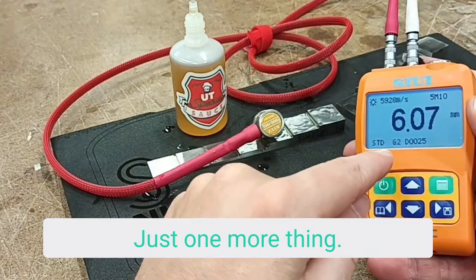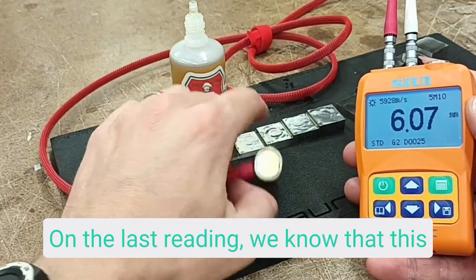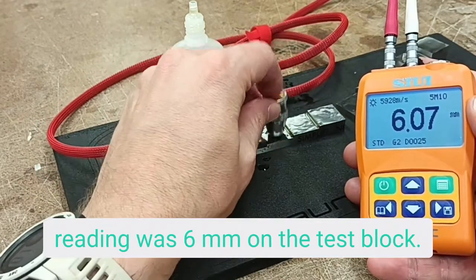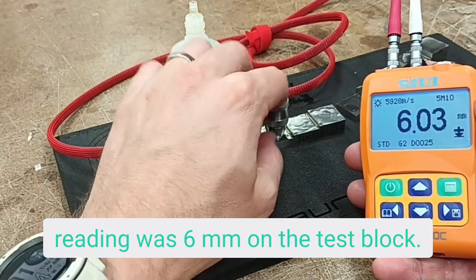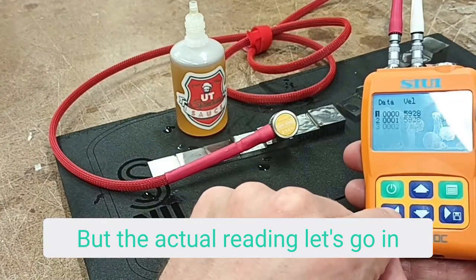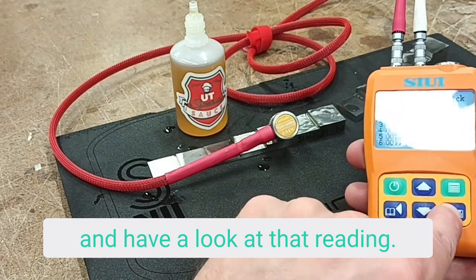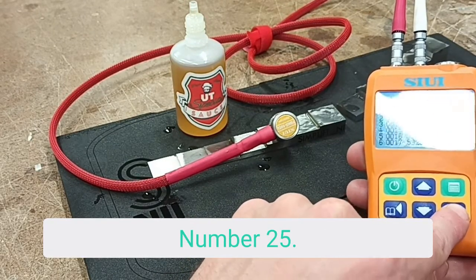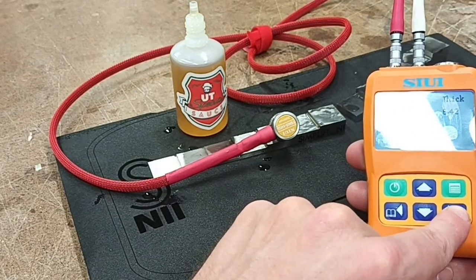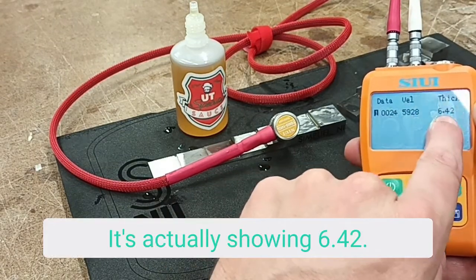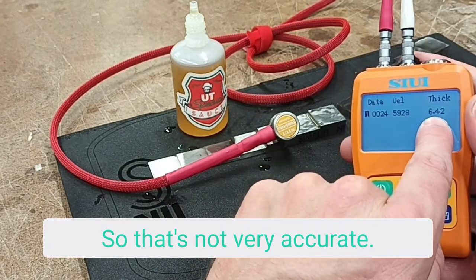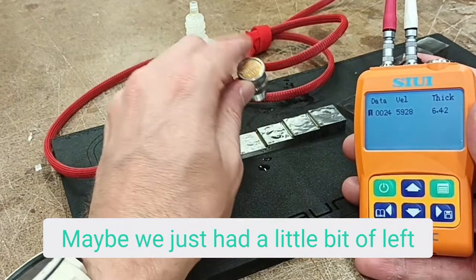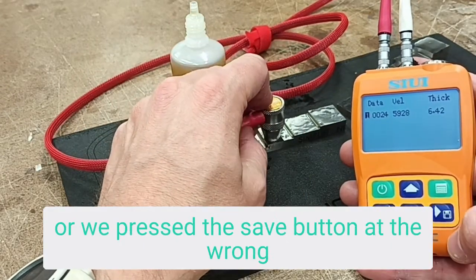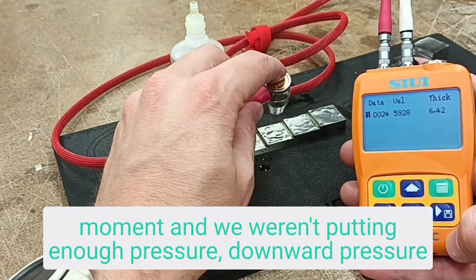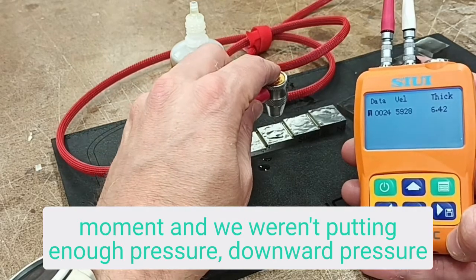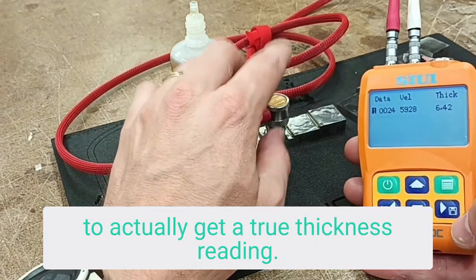Well, just one more thing. On the last reading, we know that this reading was 6 millimeters on the test block, but the actual reading, let's go in and have a look at reading number 25. It's actually showing 6.42, so that's not very accurate. Maybe we just had a little bit of lift, or we pressed the save button at the wrong moment, and we weren't putting enough downward pressure to actually get a true thickness reading.